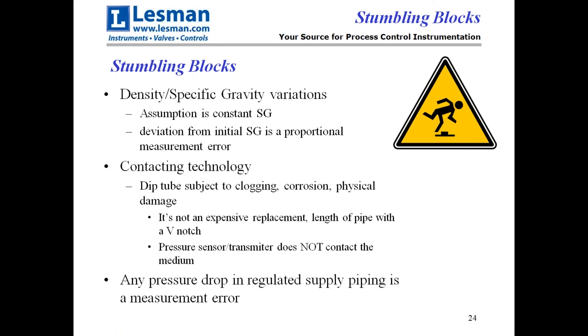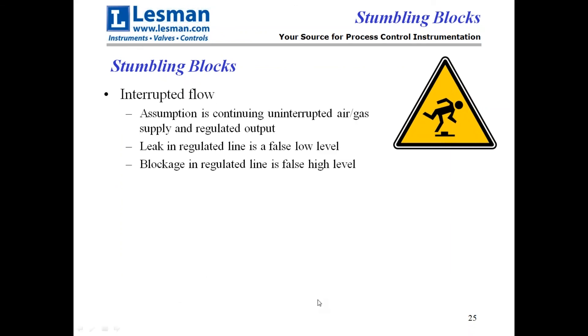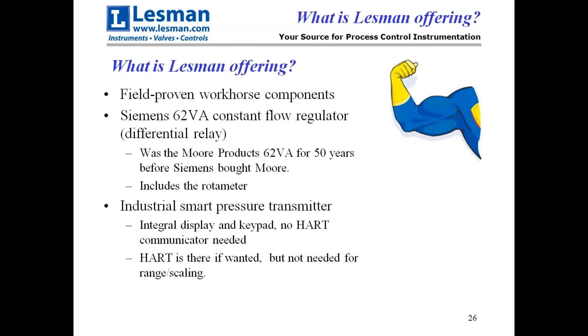What Lesman offers: field-proven workhorse components. The Siemens 62VA constant flow regulator is the same one originally from Moore Products — sold for 50 years before Siemens bought Moore, giving it a 60- to 70-year history in bubblers and making it the absolute standard of the industry. It includes the rotameter for visual flow indication. We use industrial smart pressure transmitters — Siemens units with HART, an integral keypad and display so you can reconfigure in the field without HART. We put the coalescing filter right in the panel. There's a big display on the front to read level, and an optional push-button purge — hold the button in, air flows down the tube and purges it. The panel comes built, tested, and ready to install, ranged to your specification.